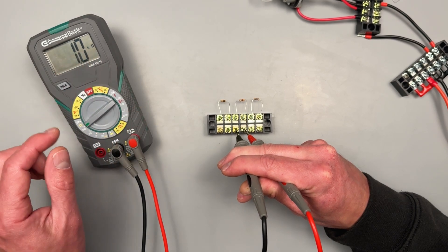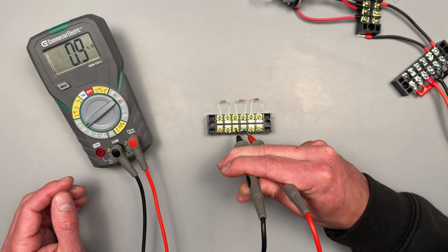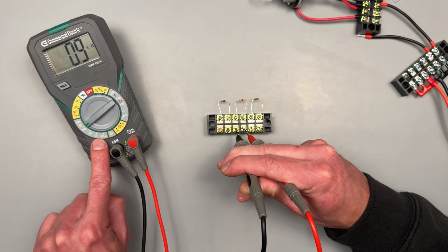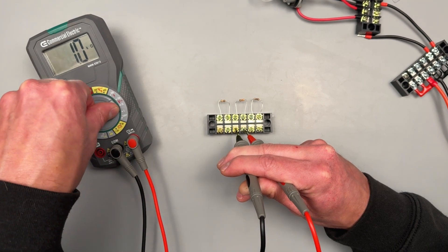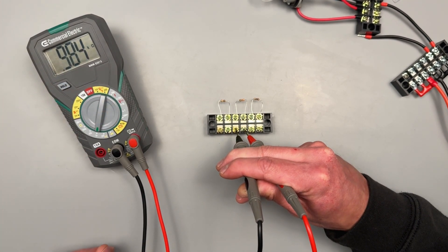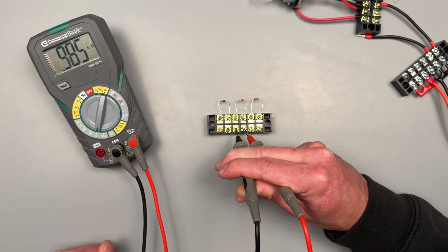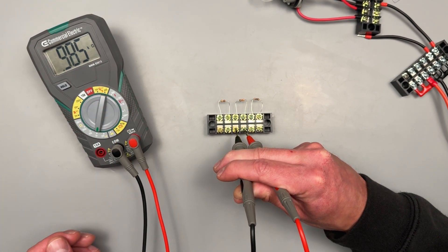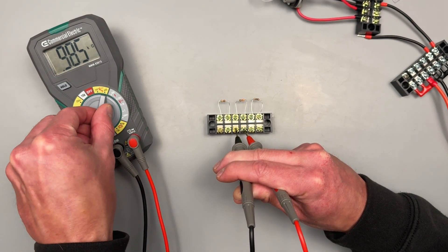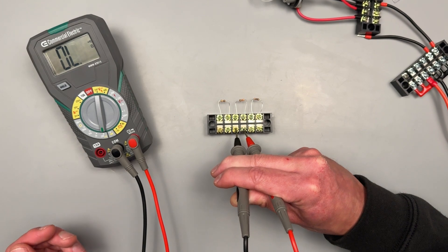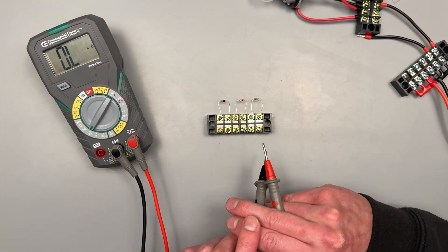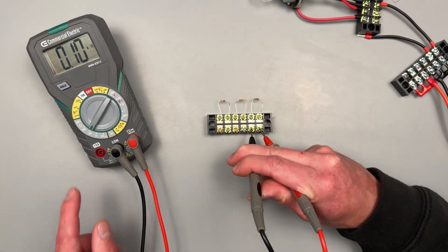Once you get a little more practice, get a little more comfortable with it, you see 1k ohm, okay, now I know in my head there's a thousand ohms. I have a 2k setting here - why don't I just skip to that one? And now I know I'll get the best resolution I can. And so this is saying we have 985 ohms. And then if I go to the 200 setting I'm out of range. Then we can hop over to this last one. We have 0.1k, so that should be a hundred. So let's go to our 200 setting. We have 98.9 ohms.